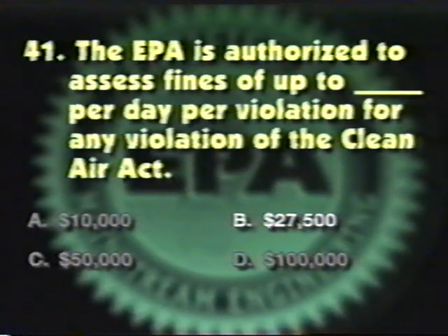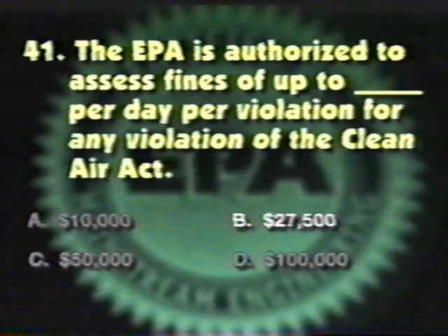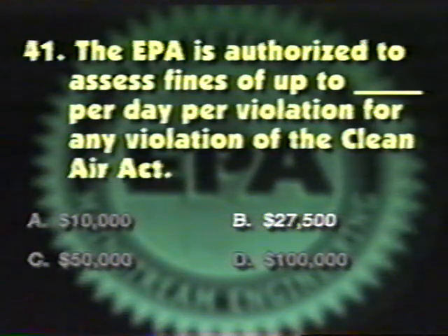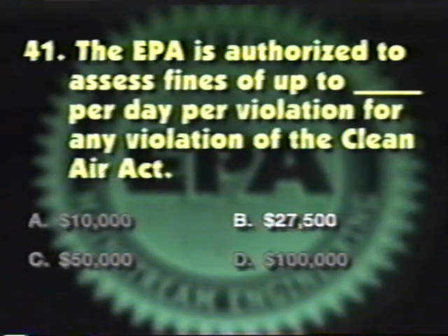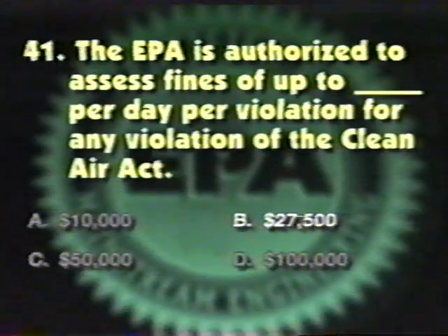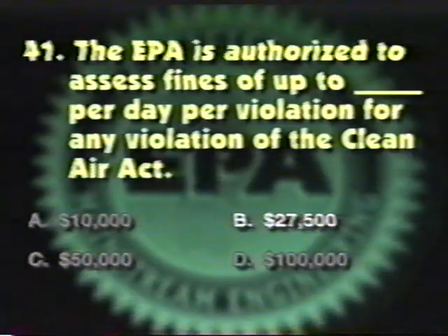The correct answer is B. $27,500. Since July 1, 1992, the EPA has been responding to tips reporting venting. Under the Clean Air Act, the EPA is authorized to assess fines of up to $27,500 per day per violation for any violation of the Act. This dollar amount is a maximum figure and is not necessarily the amount that will be assessed or paid in all cases.